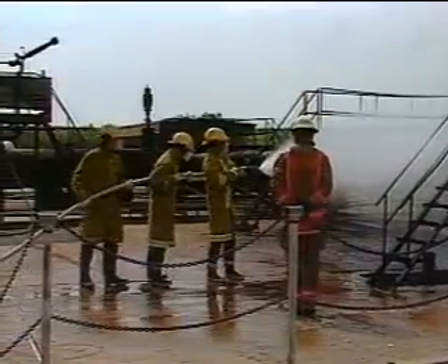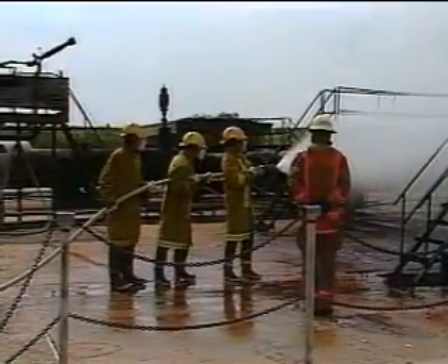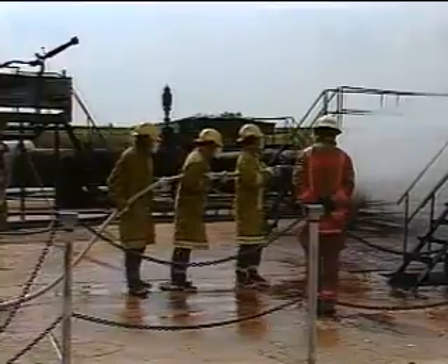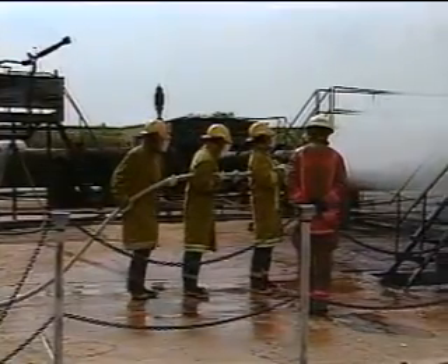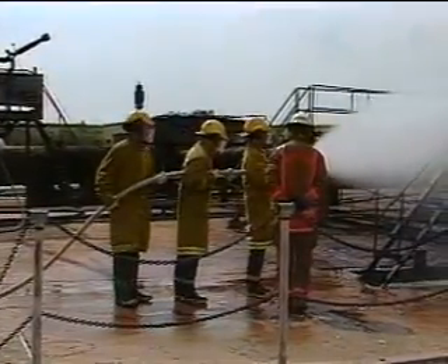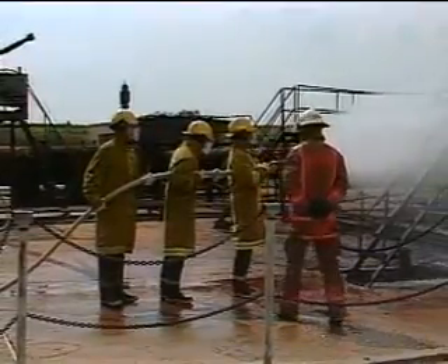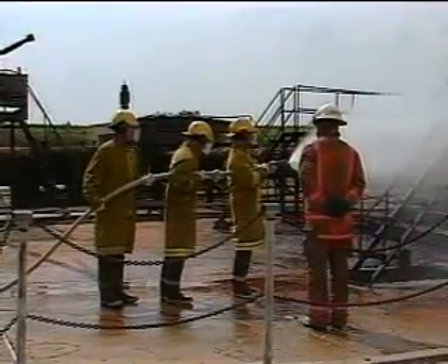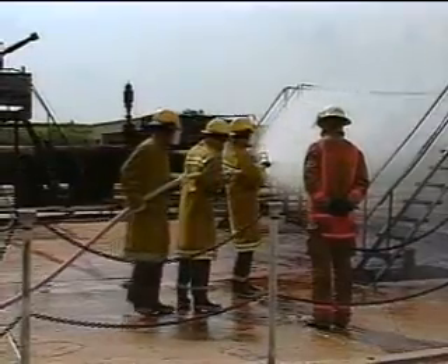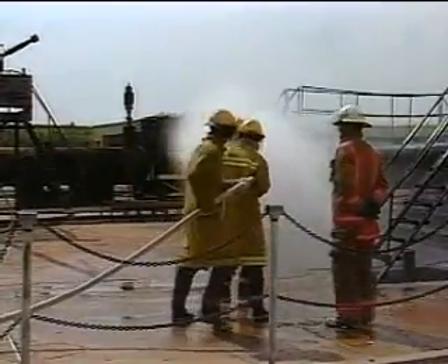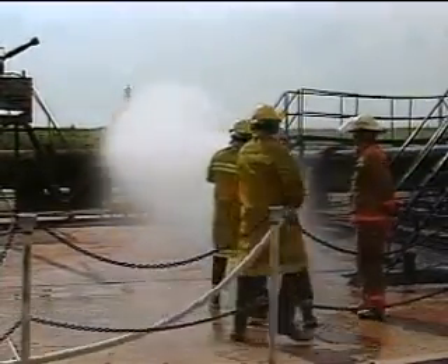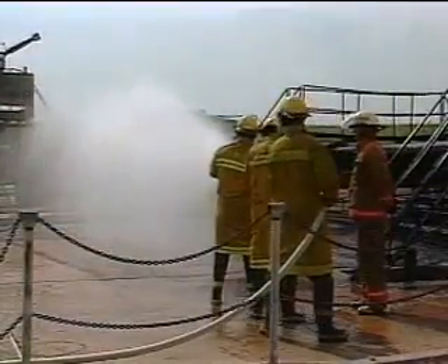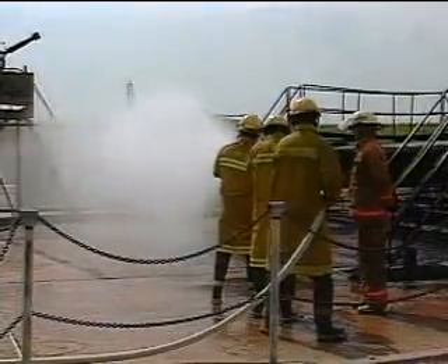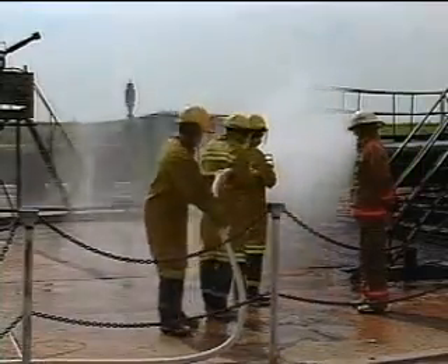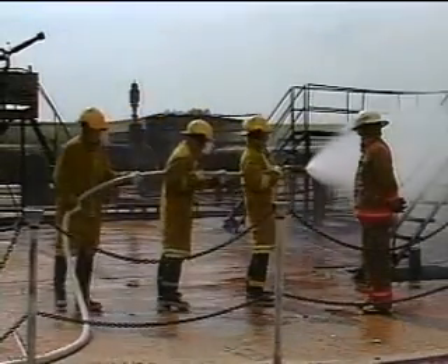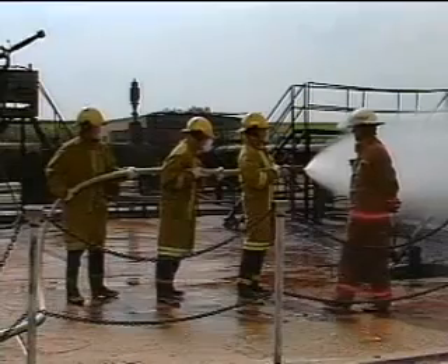The person on the nozzle controls the nozzle and the team. The nozzle should be held 1 foot in front of you, with the bail on top. The second person leans into the hose and provides major resistance to hose reaction, so the nozzle person is free to direct the nozzle. Slacking off can result in injury to the nozzle man or loss of control of the hose line. The second person must stay alert of nozzle actions and raise or lower the hose as necessary.